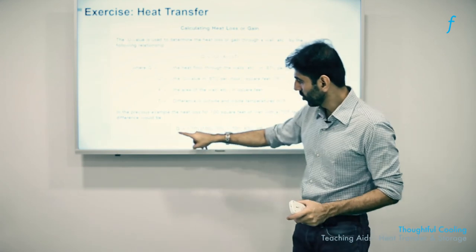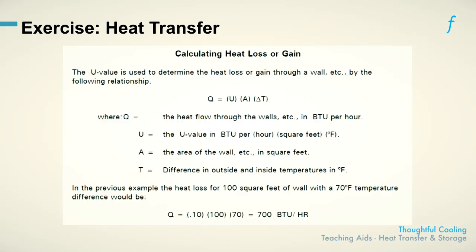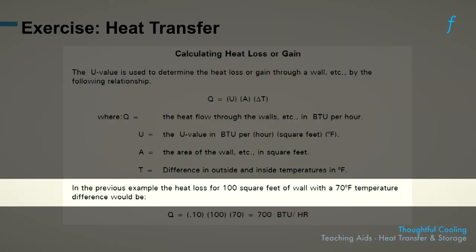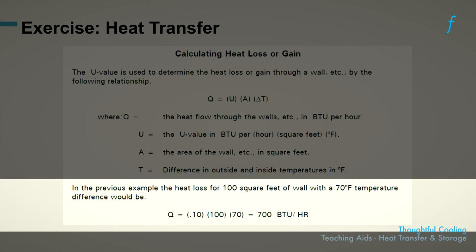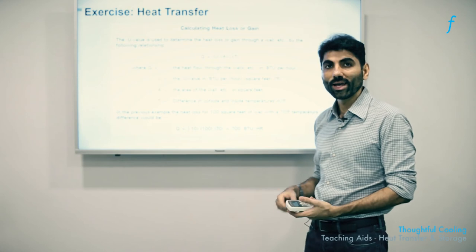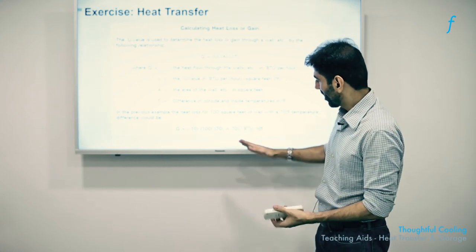In this case, it shows that the amount of heat that is being transmitted by one situation with a U value of 0.1, for example, is 700 BTUs per hour. If the U value was lower, say 0.05 rather, this Q would be approximately 350 BTUs per hour. BTUs is just a way of conveying energy, right? What we would then do is multiply that lowered BTU per hour by the hours that this wall would now be cooler for, and thereby allow us to make a good life cycle decision by comparing it to the embodied energy of the material.